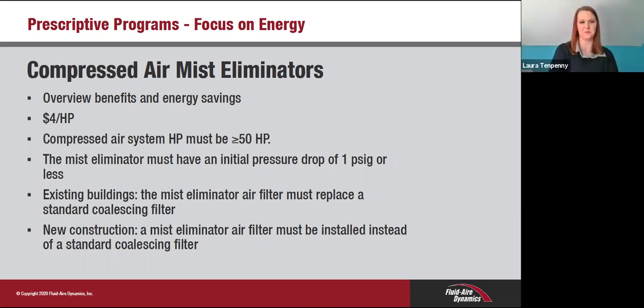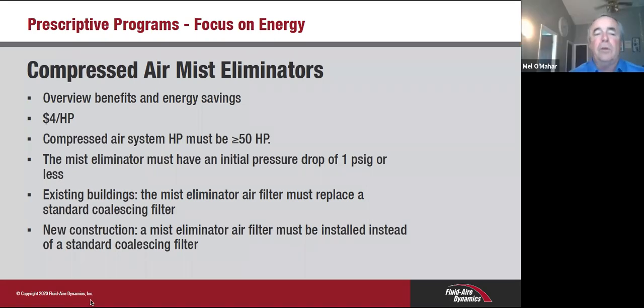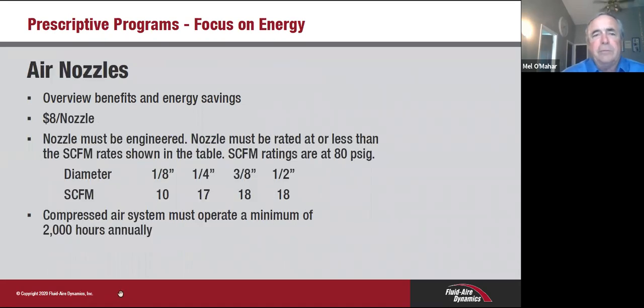I know we'll probably talk about it when we get to the heat recovery, but just the fact of how much of your energy put into your air compressor doesn't go to usable work in that compressed air. You start back calculating that, and you start realizing how much energy that simple air compressor is actually using at your facility. We talk about efficiency, but air compressors in general are not very efficient with energy. So can we go to the next slide, Mike?